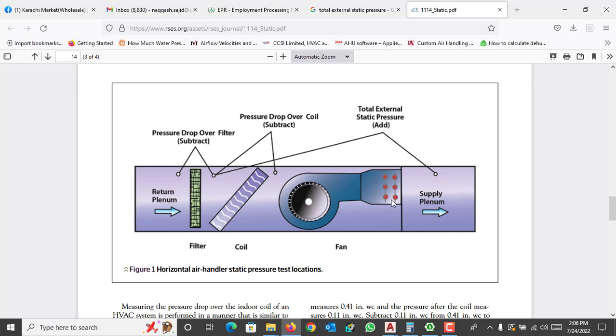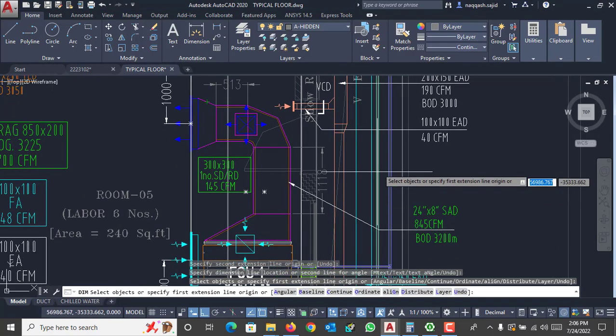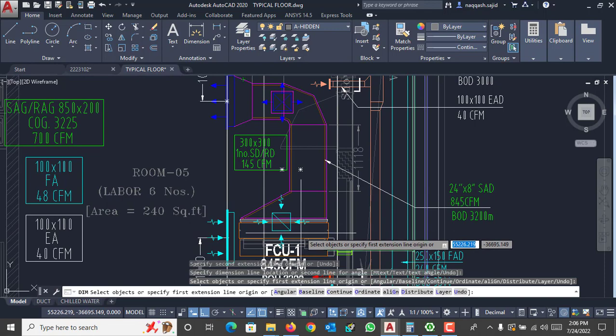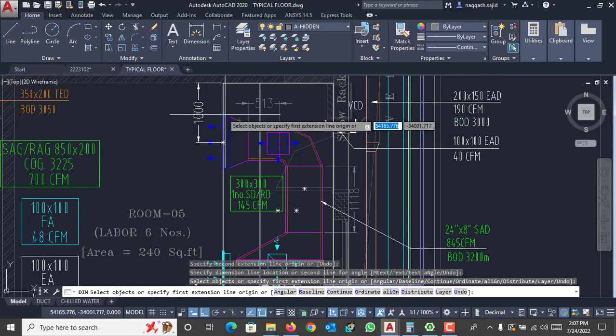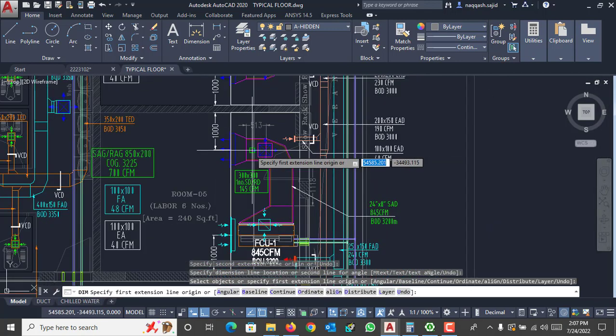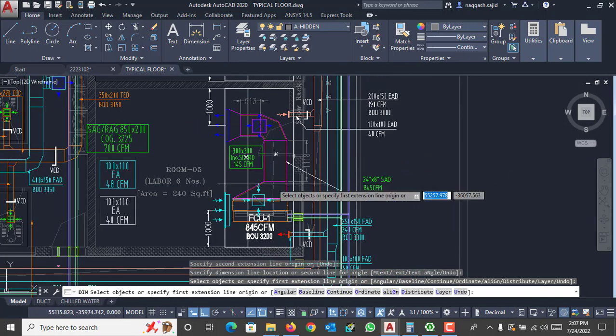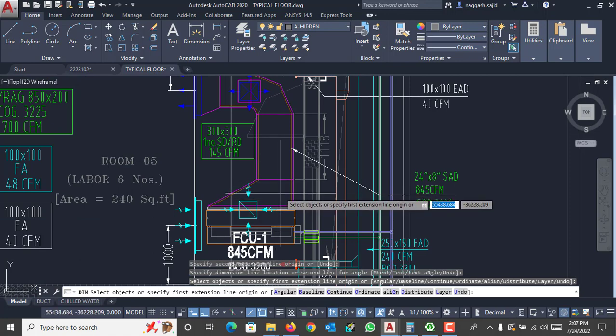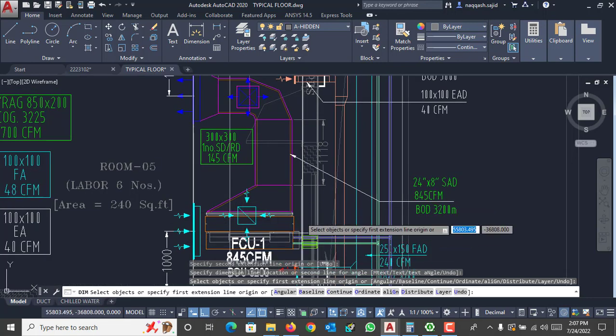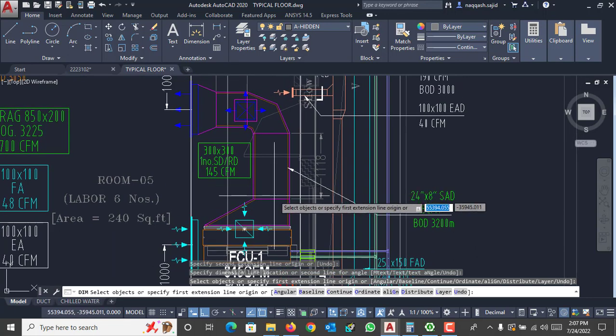I have a simple example here. You can see there is an FCU with a duct connected to it, and a grill connected with a bell mouth. If you know the external static pressure of these fittings and ducts, you can easily provide data to the manufacturer. The two main data points required by the manufacturer are the CFM (flow rate) and the external static pressure. Once you provide ESP and CFM, you can select an FCU, AHU, or fan.